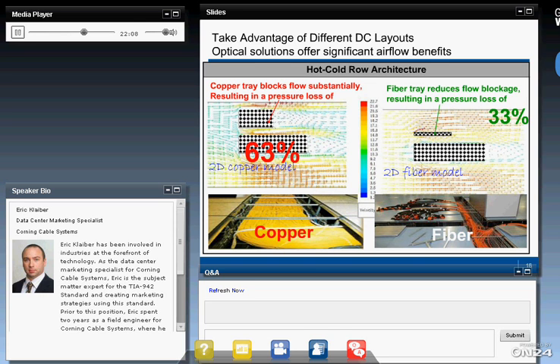So what does this also mean for the green in your pocket? Well, the U.S. Department of Energy recommends at least 24 inches of unobstructed pathway for air to flow correctly underneath a raised floor. If you start stacking copper cabling in, you may have to go from a 24 inch raised floor to a 36 or a 48. I've even seen them where you can actually walk underneath the raised floor. That adds a significant cost to your actual building and your design, to make sure you have the correct airflow in your plenum space. So you're basically getting a 30% reduction in the air blockage just by going to fiber in your underfloor cabling space.